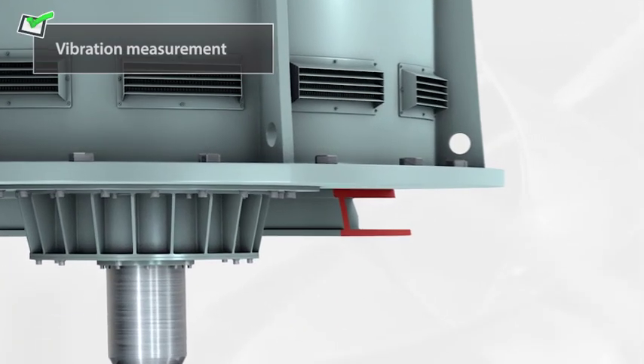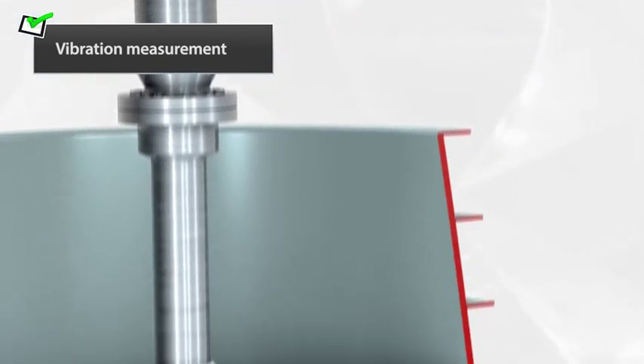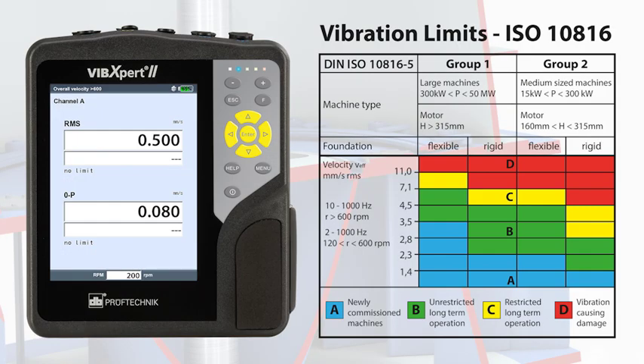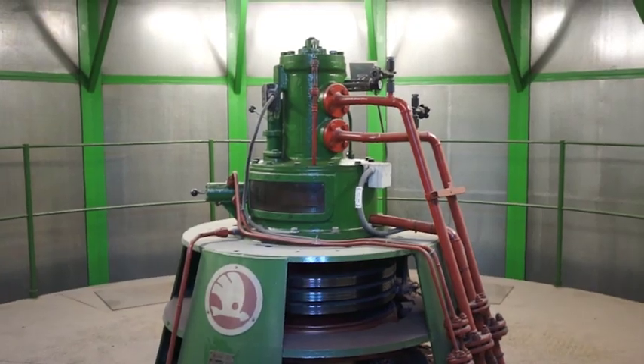At the end of the project, our engineers perform a vibration check during turbine startup using Vibexpert 2 vibration analyzer. The results show that machine RMS vibrations are below 0.5 millimeters per second and are within Zone A of ISO 10816-5. The turbine starts up smoothly with low vibration levels, thanks to the good alignment of all components.